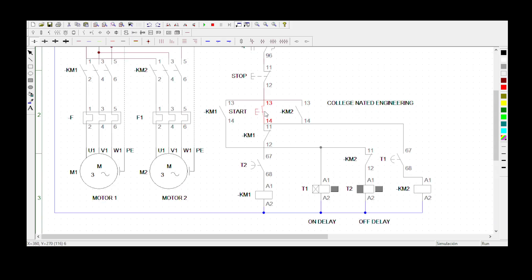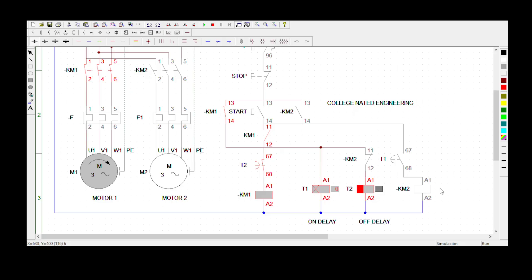When we press the start button, all coils energize except KM2. The delay-on timer starts counting and the delay-off timer is not counting. Now you can see it's at 2 seconds — once the delay-on timer becomes normally closed, it will allow KM2 to be started using the same start button. Now we can see that contact is normally closed.